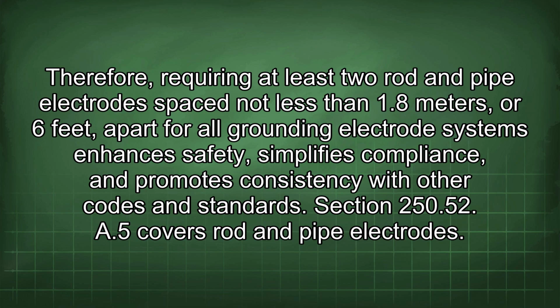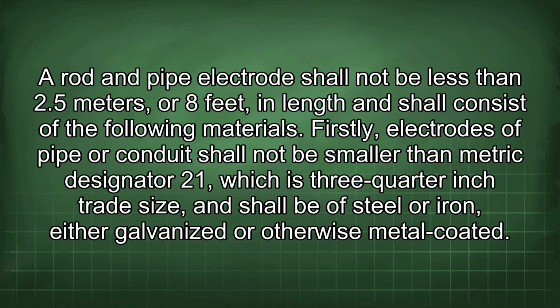Section 250.52(A)(5) covers rod and pipe electrodes. A rod and pipe electrode shall not be less than 2.5 meters or 8 feet in length and shall consist of the following materials. Firstly, electrodes of pipe or conduit shall not be smaller than metric designator 21, which is 3/4 inch trade size, and shall be of steel or iron, either galvanized or otherwise metal coated.